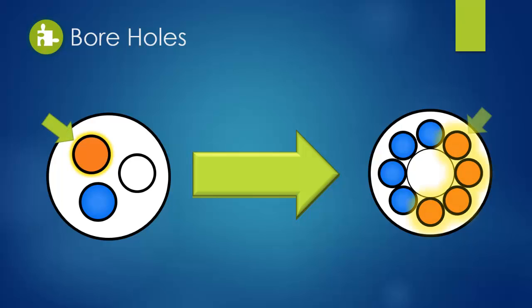The twister borehole technology provides more heat transfer capacity compared to a traditional borehole, which allows for fewer and more shallow boreholes, which will lower construction costs. The bore field will be sized based on the total cooling load, so no other central mechanical cooling or heating equipment is necessary. Component 2 is the pumps.